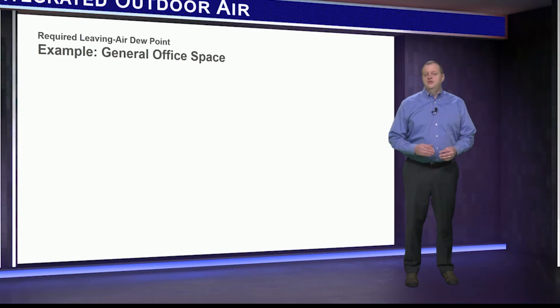Again, in a sensible cooling system like CoolSense, the dry air from the dedicated outdoor air system is the only source of dehumidification. So this air must be dehumidified to a dew point that's dry enough to offset the entire space latent load and maintain the indoor dew point below about 55 degrees.